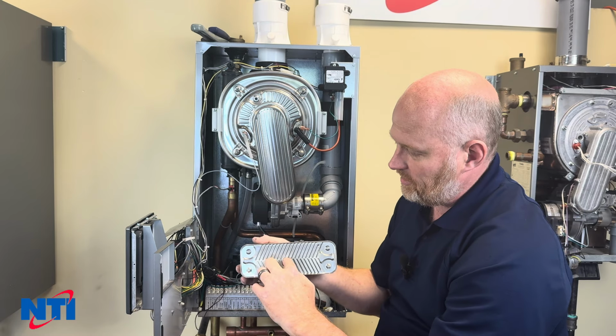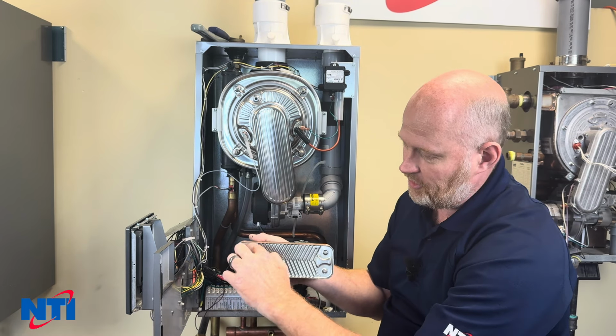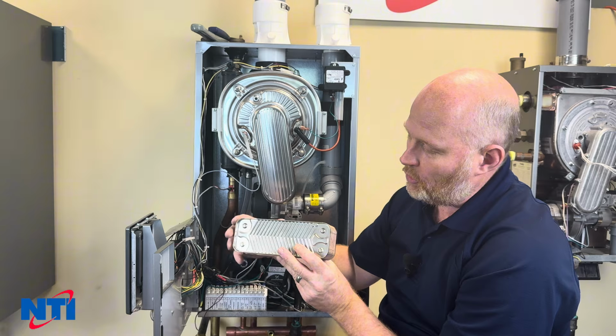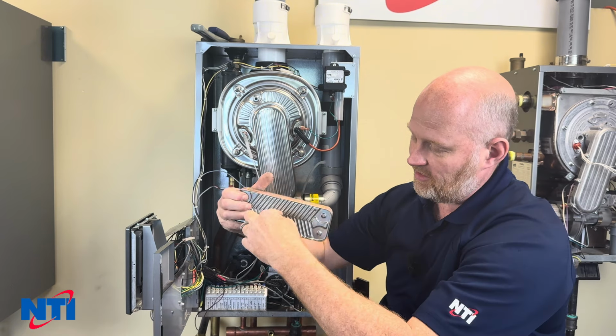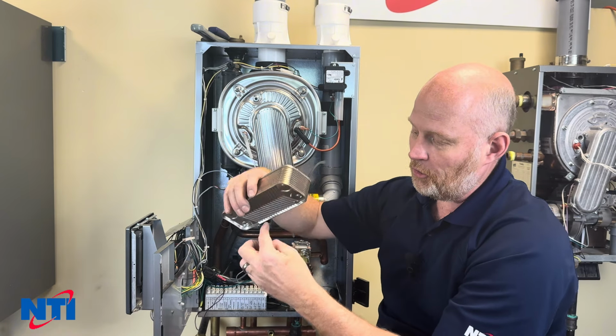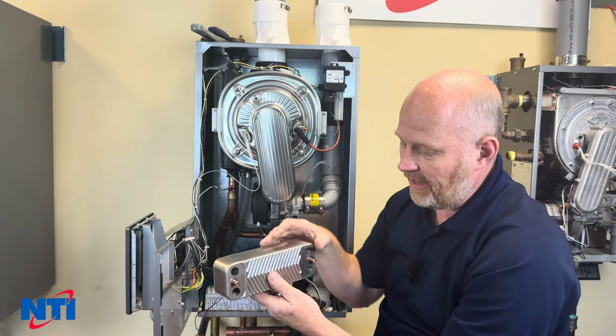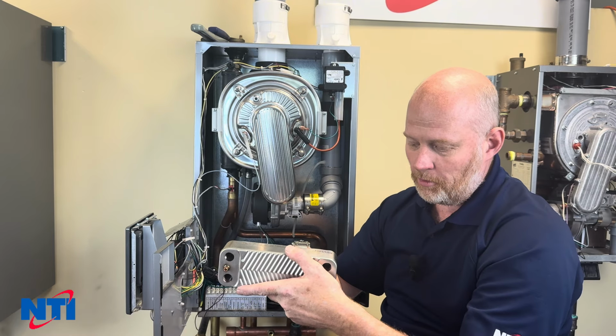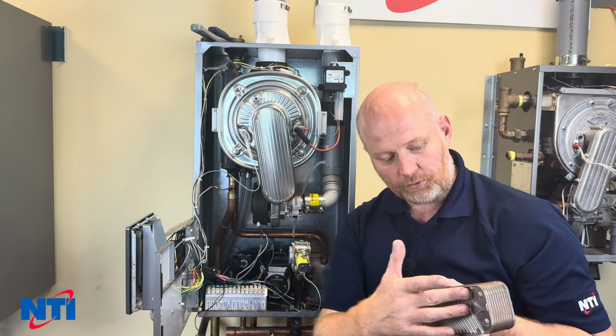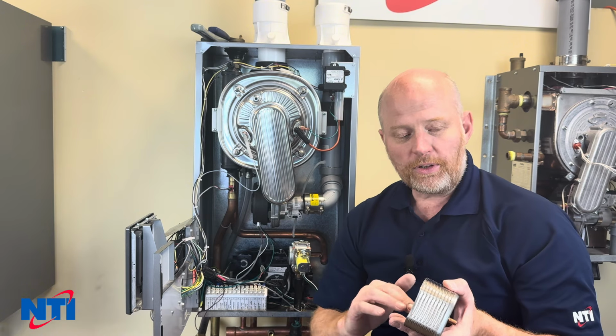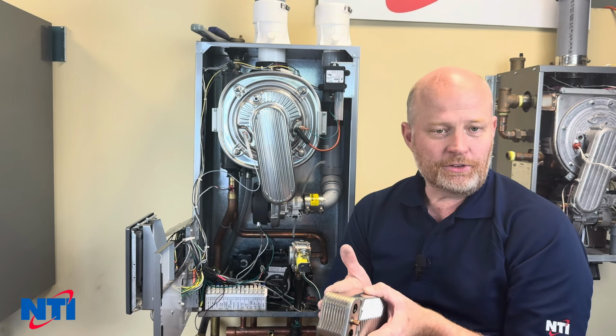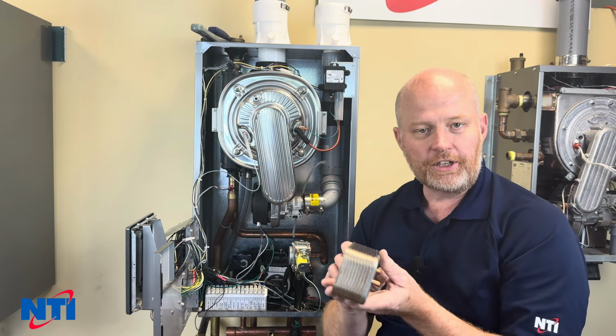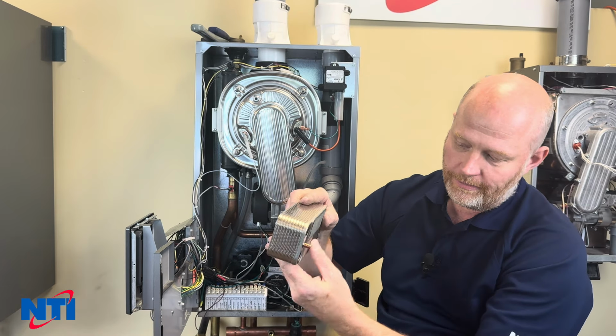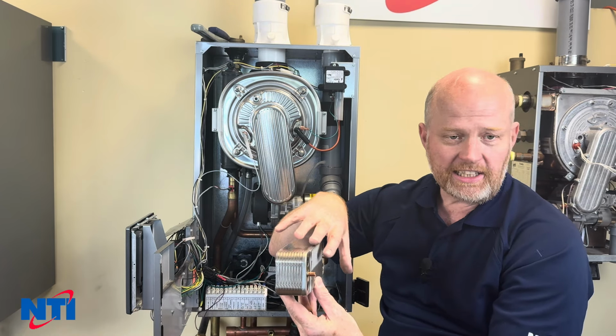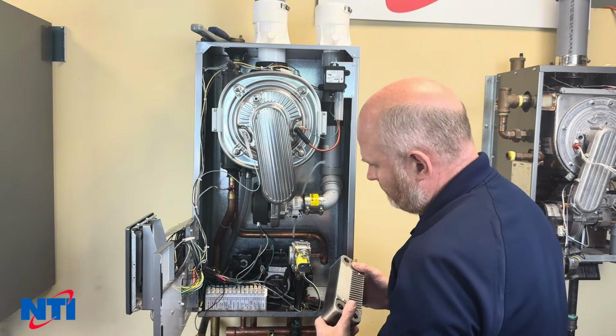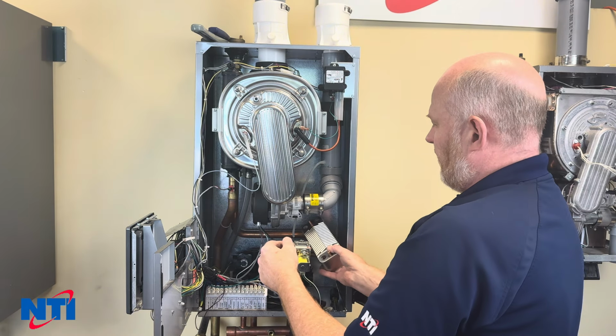There's 1 screw that's coming through the back of the boiler that sits in this recessed area. So when you go to remove it, you just twist it slightly so you can get it up over that screw. And when you go to reinstall it, you're going to do the same. That screw is facing this way from the back of the boiler, and it's going to sit inside this recessed area. If you don't know that's there and you can't see it, it makes this a rather difficult job. Once you know it's there and you can account for it, you sort of feel it with your finger, slide this over it, and then there's plenty of space to get this back in. So we're going to put this back in now.